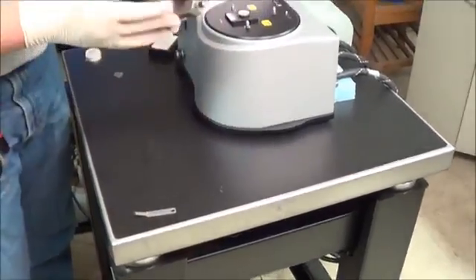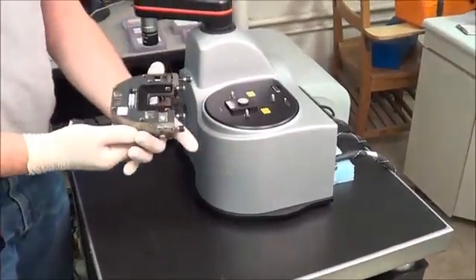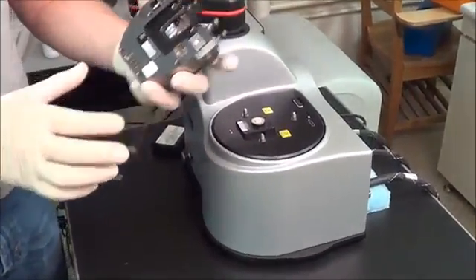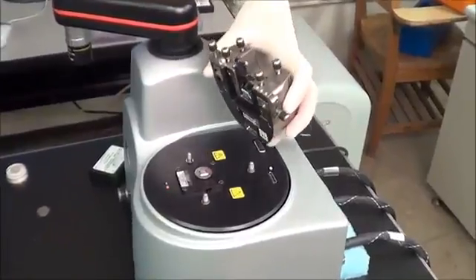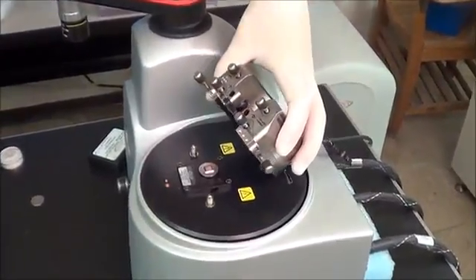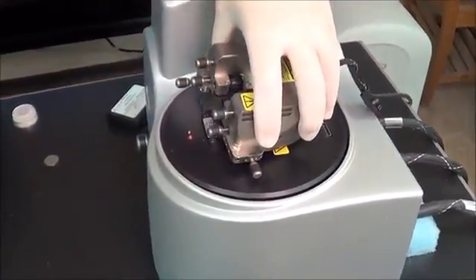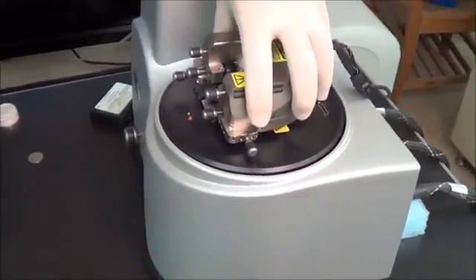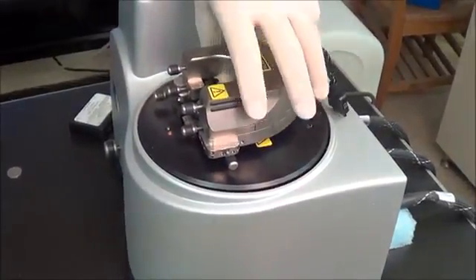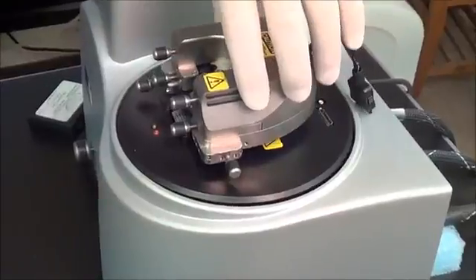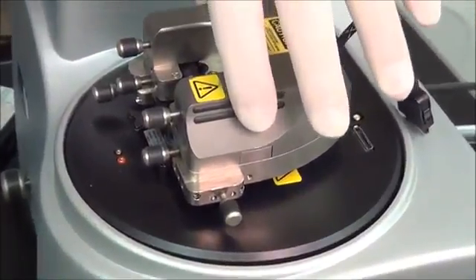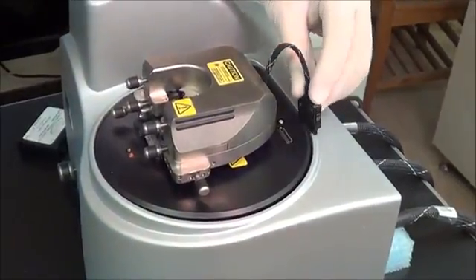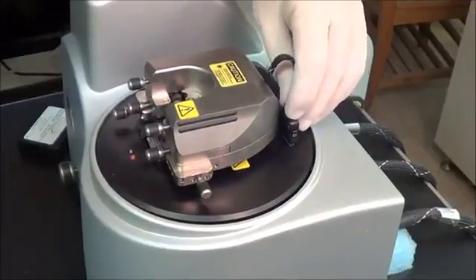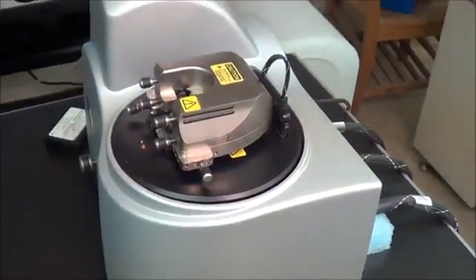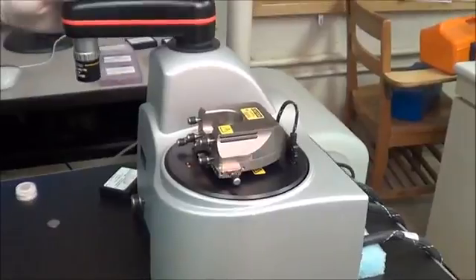Now we place the probe mount back into position. Take note of the 3 points that it fits on. Again, we start with the back point before resting it on the front two. This helps to ensure that our cantilever does not bump the sample. Once in place, we gently rock the mount to ensure it's well seated. We plug the mount into the stage, and then we'll swing the microscope back into place. We're now ready to start the program and scan the sample.